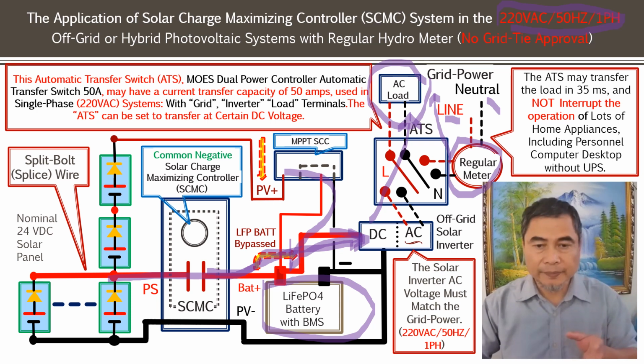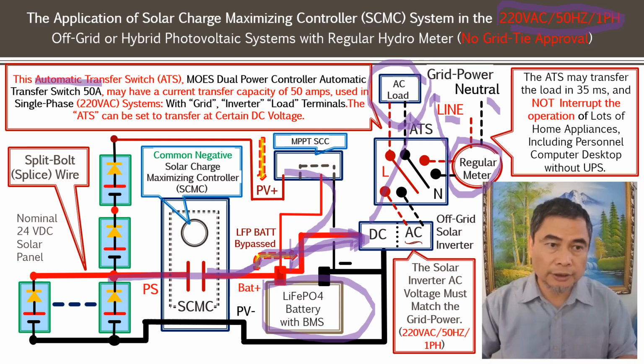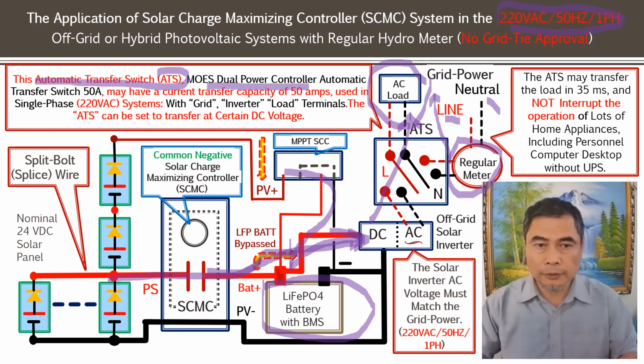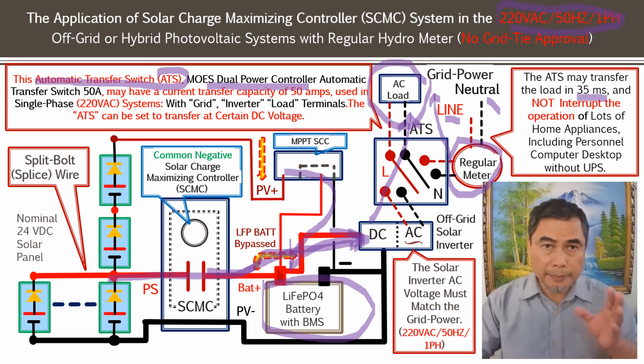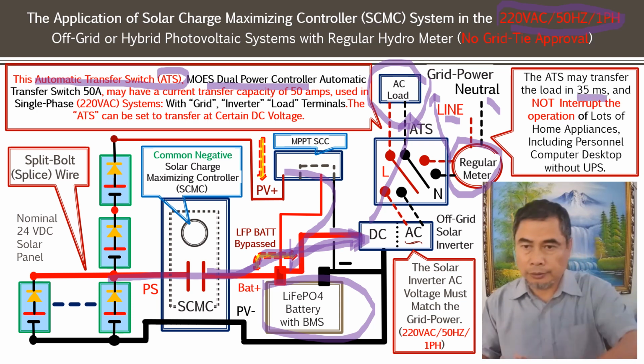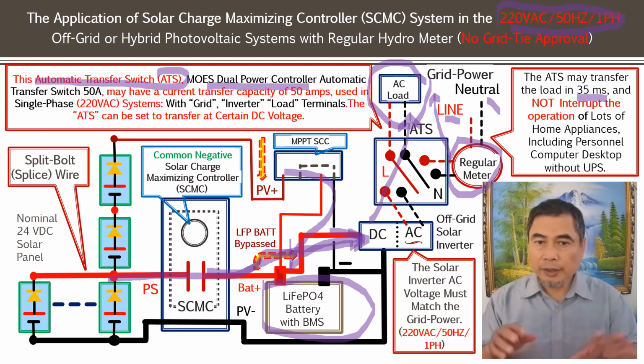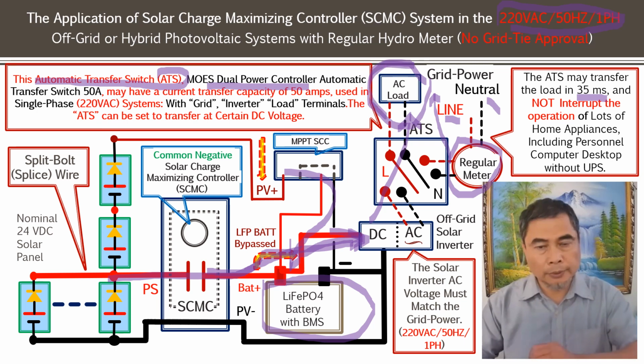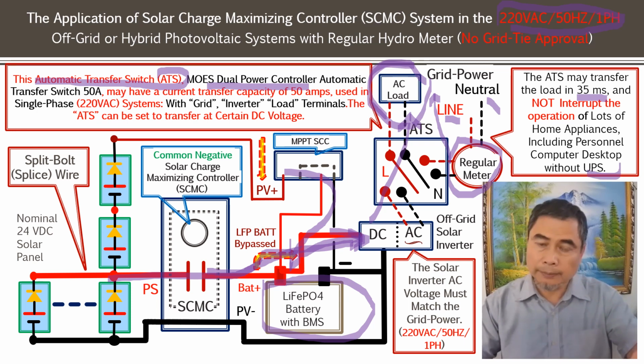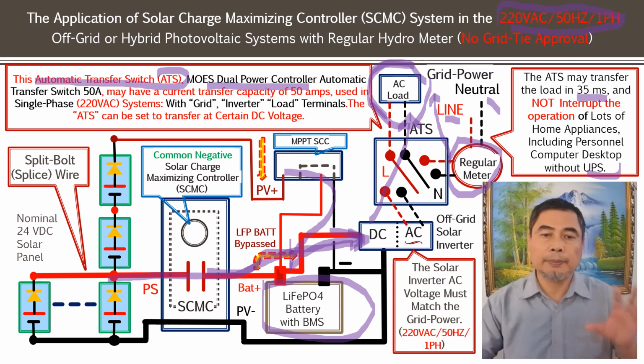And the system will rely on an automatic transfer switch. This MOES automatic transfer switch is quite reliable. We tested this transfer switch for years. They transfer the power in 10 milliseconds, depending on grid to solar or solar to grid, maximum 35 ms. In either case, you can have a load here that includes a personal computer. It will not shut off the personal computer even without a UPS connected. For lots of appliances, say the lighting fixtures connected, you don't realize there's a switch change.